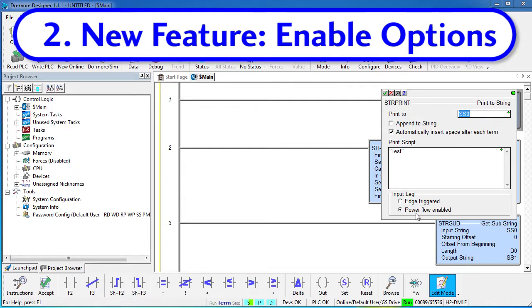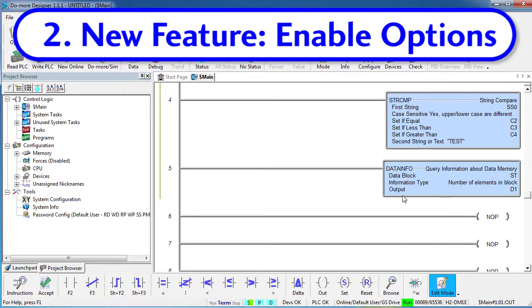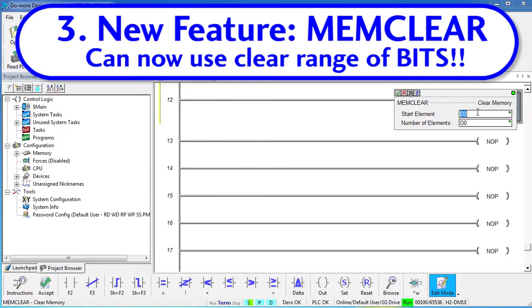A number of string functions now have the ability to be either edge triggered or power flow enabled. That's really handy when using these in ladder code. That ability has also been extended to the instruction that queries information about data memory — again, very handy. The memory clear instruction can now clear a range of bits. Before you were limited to numerics and structures; now you can specify bits that you want to clear. You start at bit C2, specify how many you want to clear and away you go.